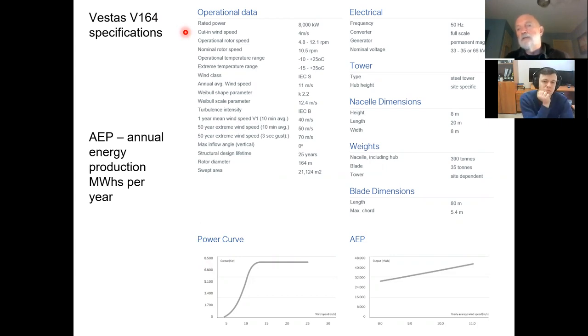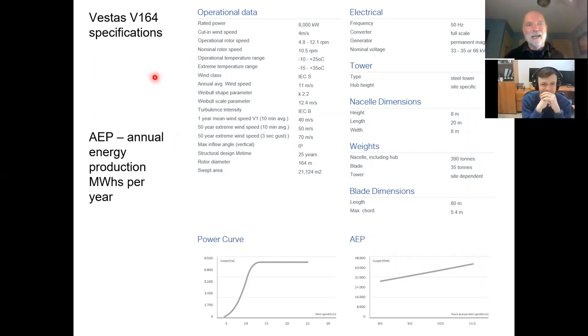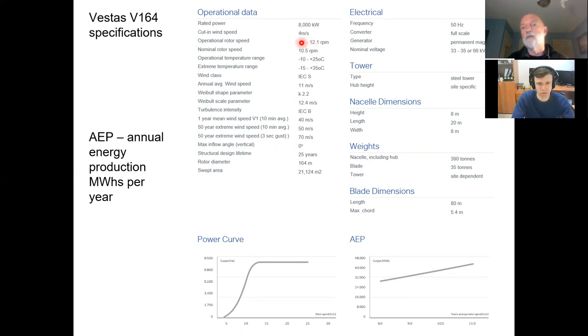Going through the specifications: first, the rated power is the maximum power the turbine produces — whenever you hear a turbine size given in megawatts, that is the rated power. Then there's the cut-in wind speed, which is the lowest wind speed at which power is produced — here the power curve rises from zero at 4 meters per second. The operational rotor speed ranges from 4.8 to 12.1 rpm — quite slow for such large turbines.